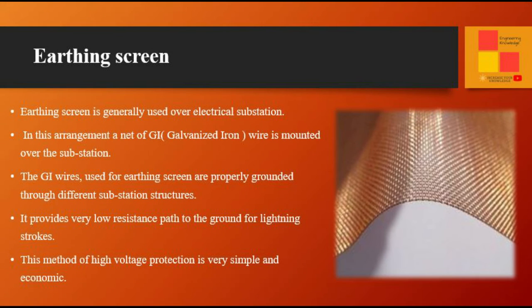Earthing screen is generally used over electrical substations. In this arrangement, a net of GI (galvanized iron) wire is mounted over the substation. The GI wires used for the earthing screen are properly grounded through different substation structures. It provides a very low resistance path to the ground for lightning strokes. This method of high voltage protection is very simple and economical.